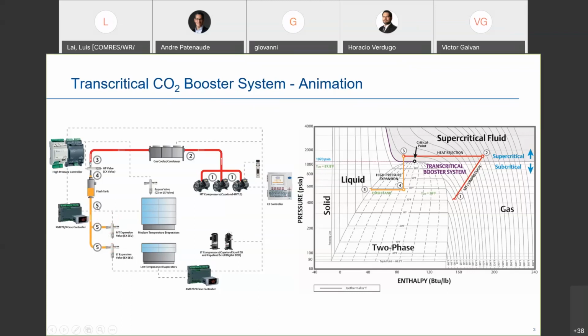From 5, the pressure is all the same. And then it goes through the expansion valve to a medium temp, and medium temp goes off to a suction area. Again, the liquid at 5 goes to a low temp valve, and the pressure drops possibly from 500 or 600 pounds down to maybe 200 pounds, a large pressure drop. Up here, you've got another area from 4 to 5. What we want to do is try to maintain a constant pressure in this tank all the time.